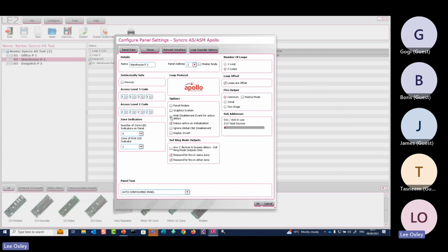You can add the LED. There's an LED that comes up on the panel that you've got a delay on this particular panel. I don't have that ticked. Why have that LED not lit? But the customer may not want it lit. He just wants the power LED. But I wouldn't add the disablement for the delays. So I'd keep that off. I want that LED on the panel.